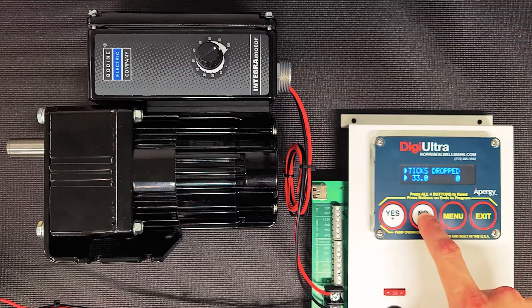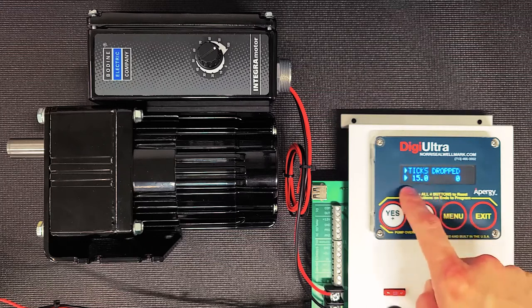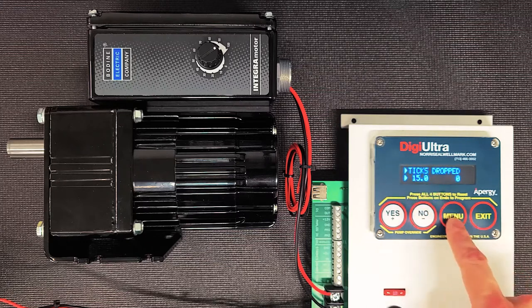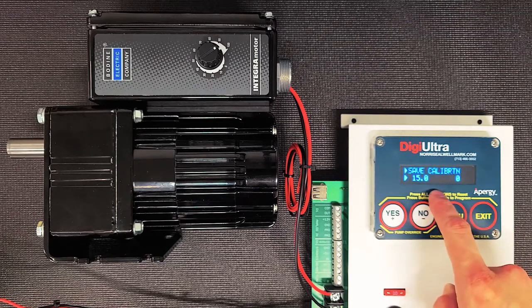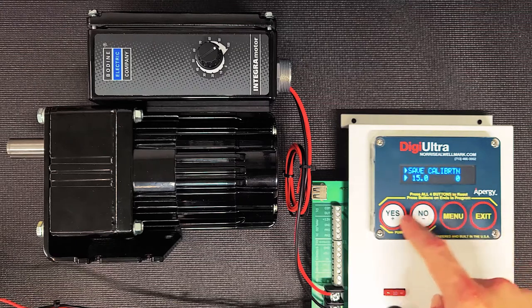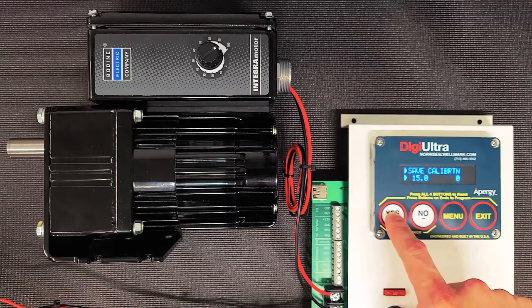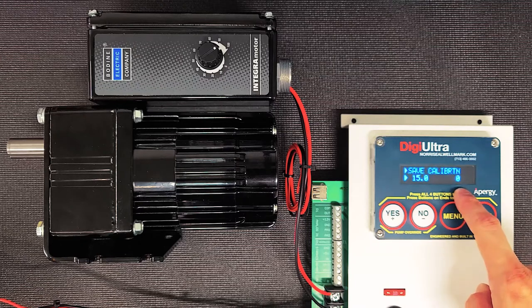So in a 5 second test, let's say we count the ticks and we see that 15 ticks were dropped in the rate gauge. Once you get the number that you're looking for, press menu to go to the next screen. It's just going to double check that you want to save the calibration, and you can verify those numbers look good and press yes to advance to the next screen. The number that's shown here on the right is actually the pulses that were read during the test, which is another thing that's measured.